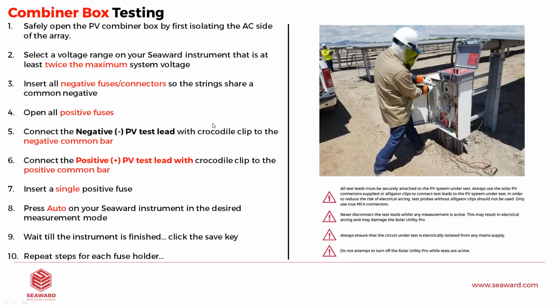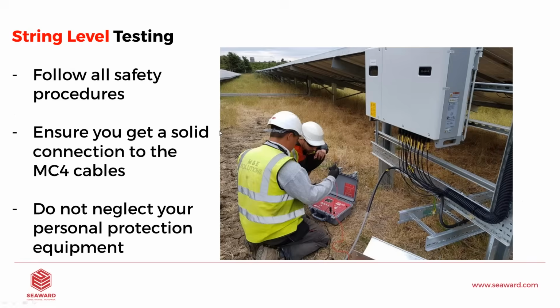So as you can see, with this method, we can very easily and quickly test a full combiner box. So we're testing polarity, open circuit voltage, short circuit current. We're also gathering irradiance and temperature. And once we get that data from the instrument, we're going to see how they compare to standard test condition values.